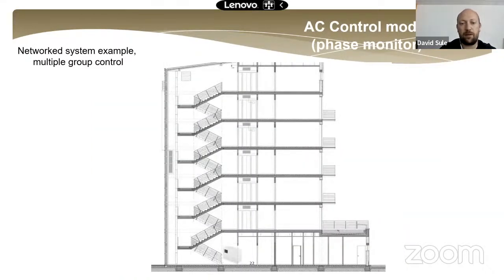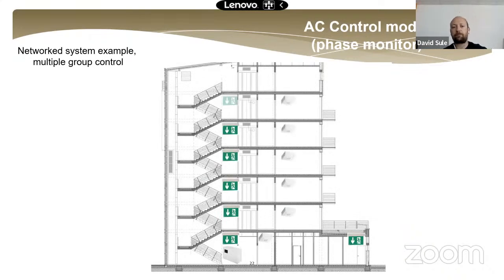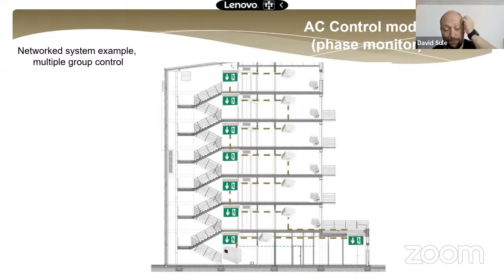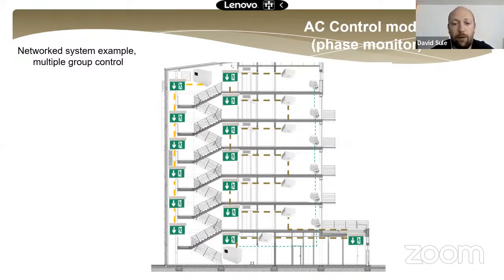Here are another pictures of a big office building with 6 floors. We have different panels in the building. For example, this is a self-contained battery panel, but the DC 24 volt panel works in the same way. We can see the sub dBs on every floor, and we install the AC control units in every sub dB. We have 2 panels in the building, and we connected the panels to a network switch.